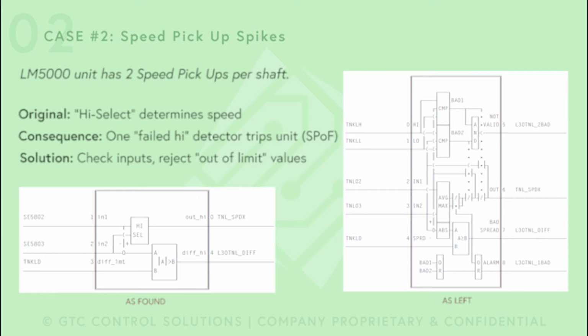And if both work okay, both are within the acceptable limits of operation, the block will calculate the average of the two. In speed pickups, the average is basically the value they read because they're really very, very close to one another. But for instance, in lube oil or bearing metal thermocouples, the average of the 2 thermocouples may give a better indication of what the actual temperature is than just taking the high value. And with this, we conclude the discussion of the 2 single point of failure cases that we wanted to present.